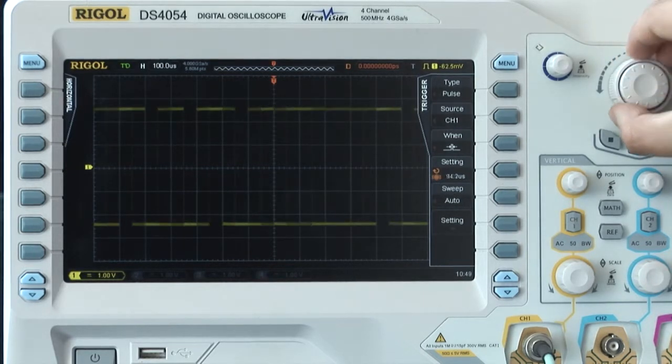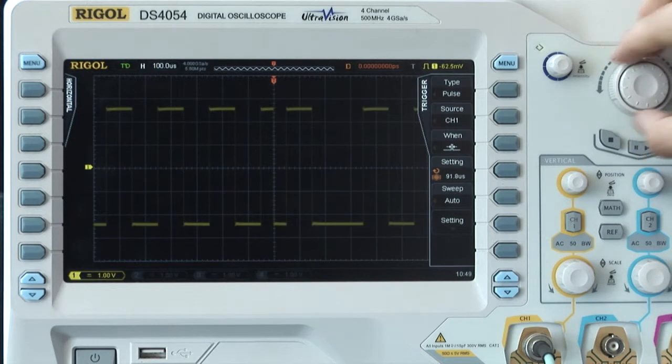Now let's choose the pulse trigger. Since the minimum pulse width of the waveform is 50 microseconds in this example, we should set the pulse condition as positive pulse larger than and set a pulse width value larger than 50 microseconds. Now we can see the waveform triggering has stabilized.